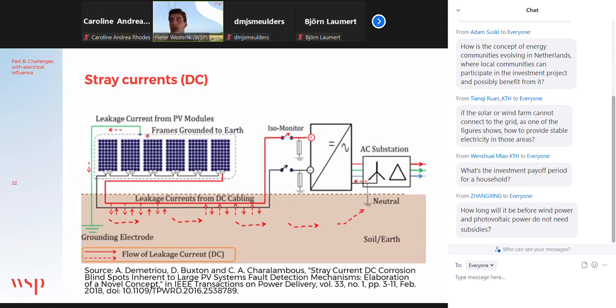And what we see is that probably the highest risk is from the DC cables that are put directly into the ground. Typically, these cables do not have an earthing screen. They only have a polymer insulation around them. And if these polymers degrade over time, or if they are damaged, then it is possible that larger currents will leak into the ground. And like with the short circuit that we saw for the high voltage system, you will get a voltage drop in the soil, and close to the point where the current is going into the ground, you will have a higher voltage, and close to the earthing system where the current is leaving the ground, you will have a lowered voltage of the soil, a negative voltage, or the other way around.